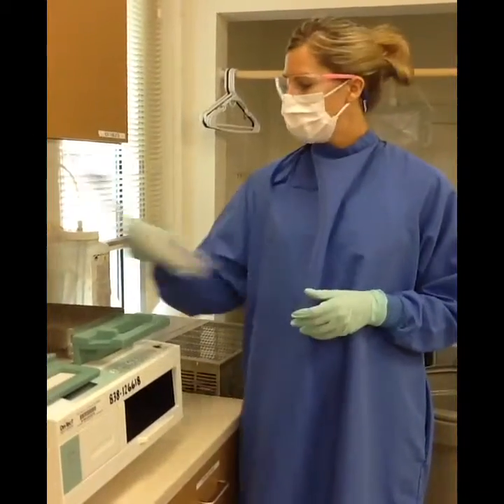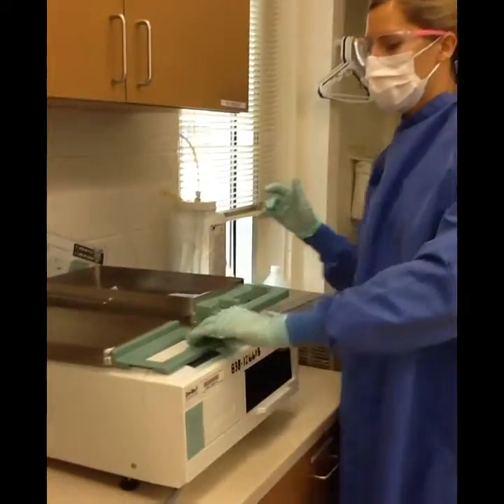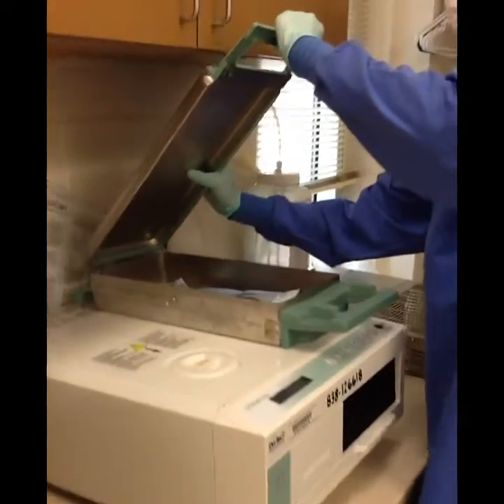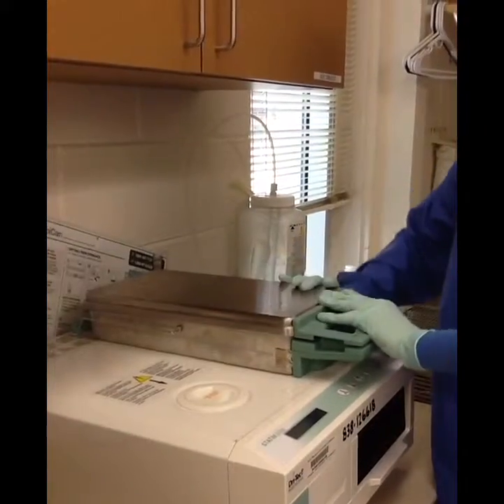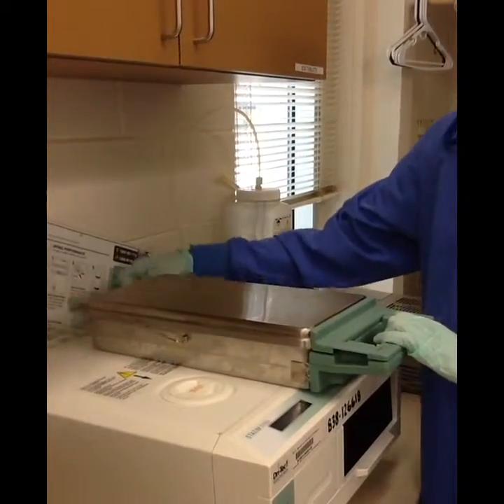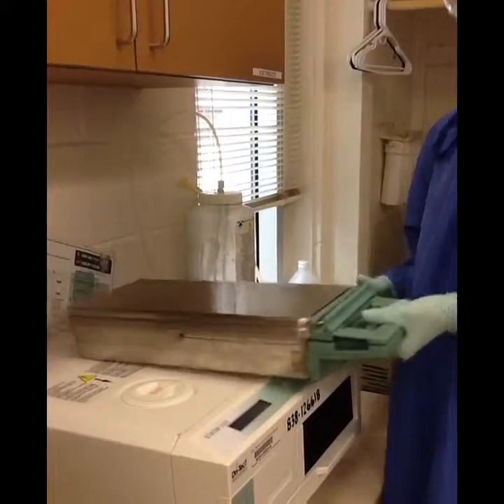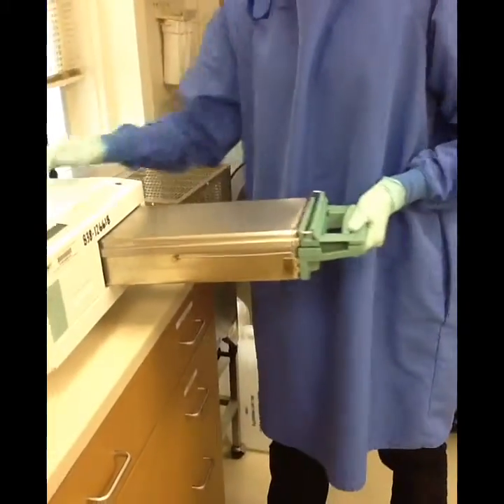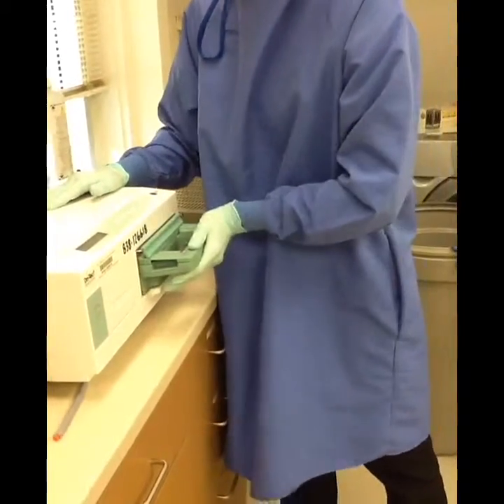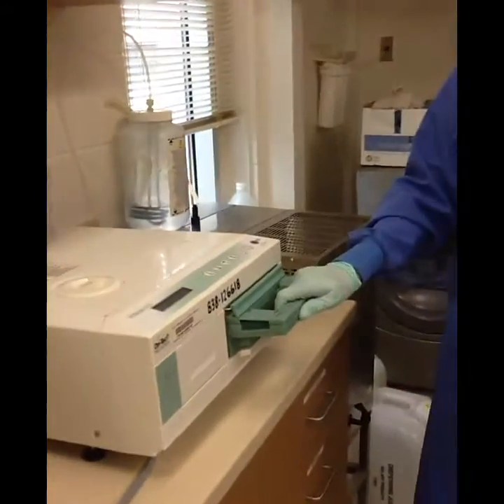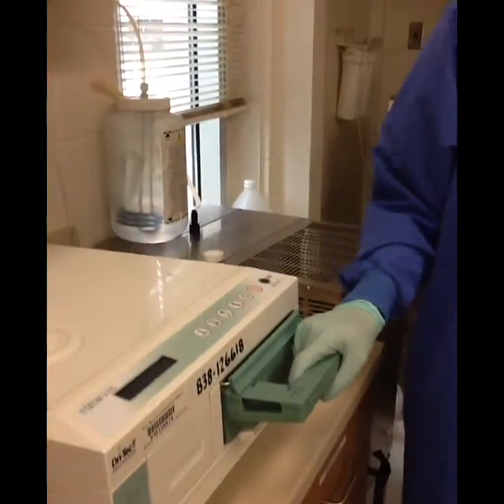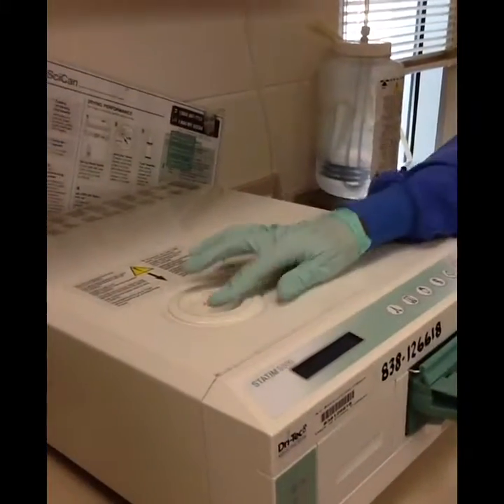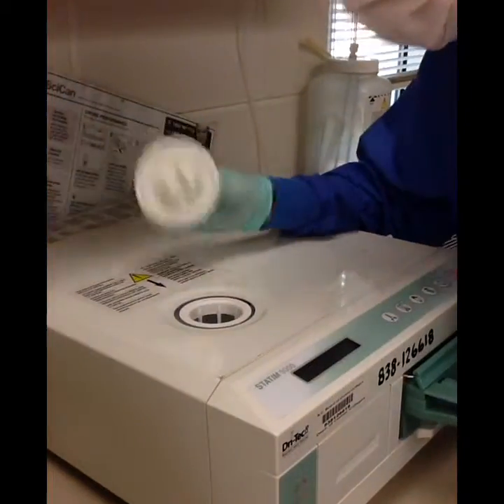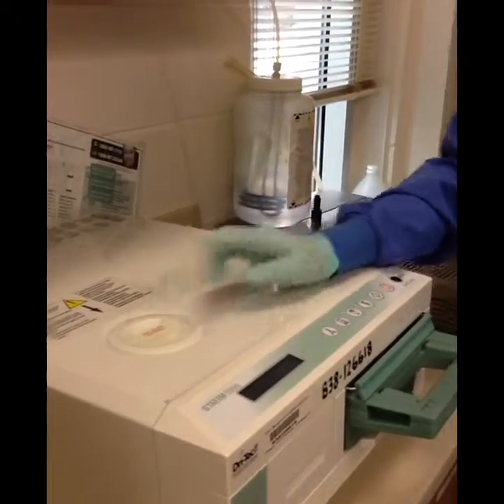Load STATIM cassette loosely. Do not overload. Close cassette lid until you hear a slight snap. Hold the cassette handle in one hand and carry the handle in the other. Place the end of the cassette into the unit and drop the carry handle into the closed position. Gently push the cassette until you hear a click. Check the water reservoir for adequate levels of distilled water. Select the appropriate cycle, wrapped or unwrapped. Press start.